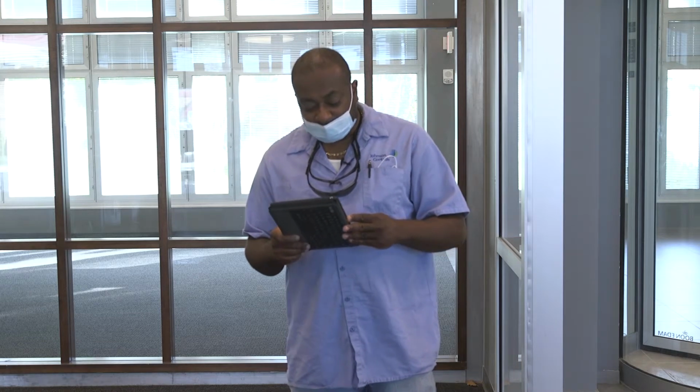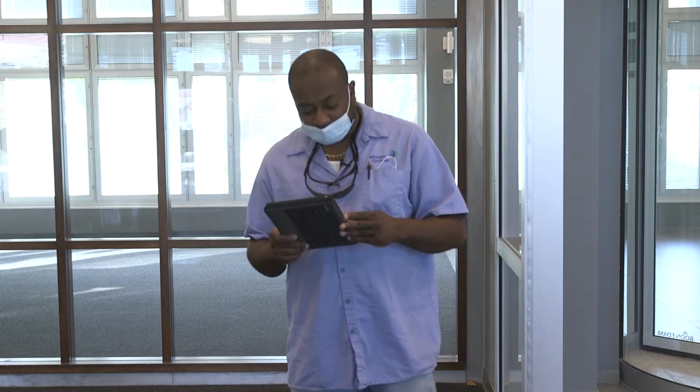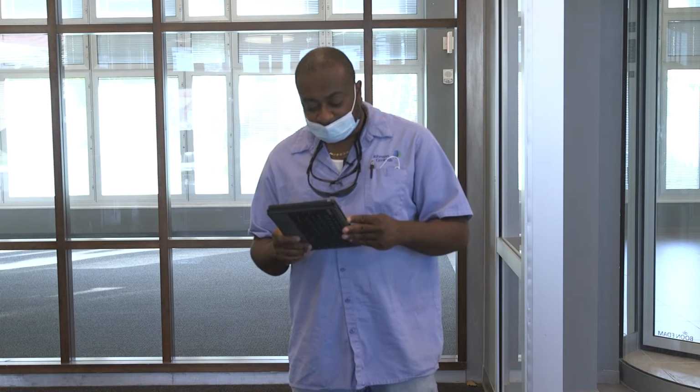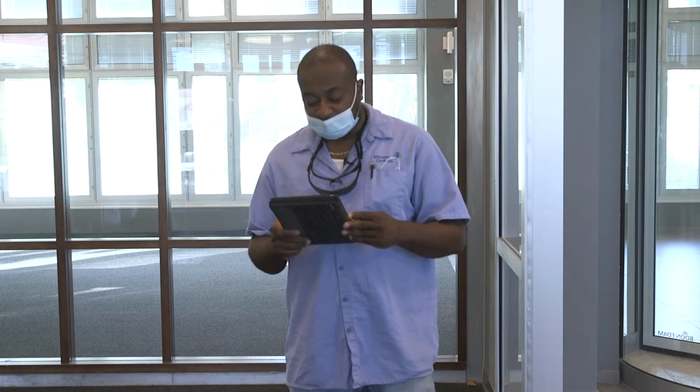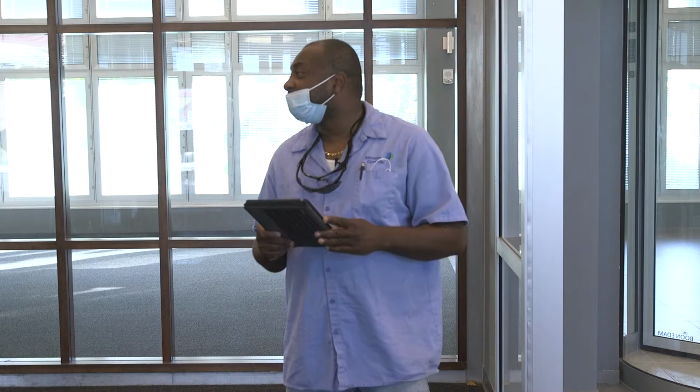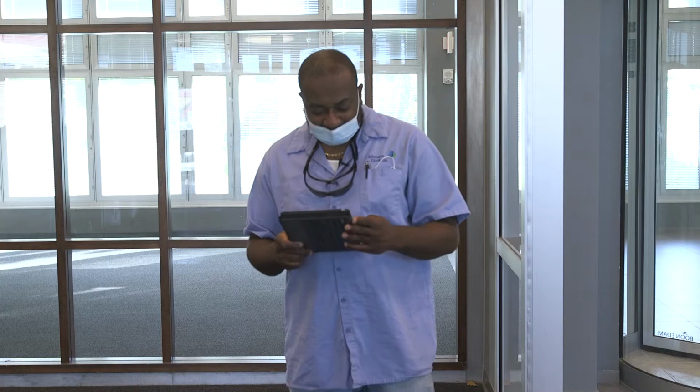Relay BR1 controls the coil for contactor M1. Contactor M1 controls the indoor fan motor, which is fan motor 1, FM1. They break it down in abbreviations. So when we go by the unit, if there's anything you don't understand here, we can point it out and go over it at the actual unit.